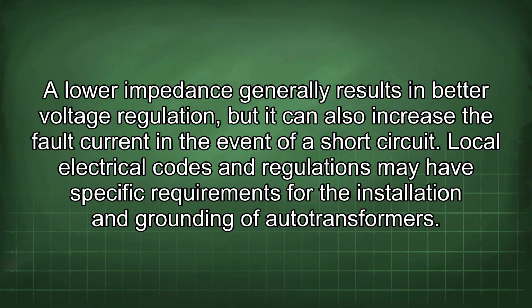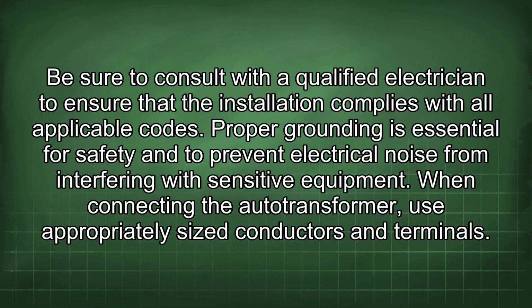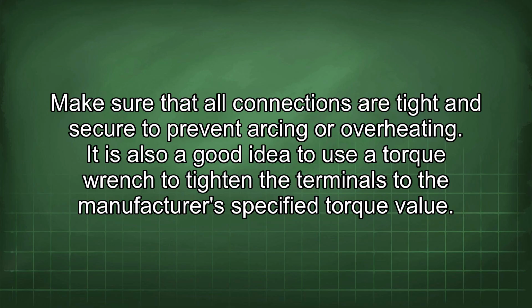Local electrical codes and regulations may have specific requirements for the installation and grounding of autotransformers. Be sure to consult with a qualified electrician to ensure that the installation complies with all applicable codes. Proper grounding is essential for safety and to prevent electrical noise from interfering with sensitive equipment. When connecting the autotransformer, use appropriately sized conductors and terminals. Make sure that all connections are tight and secure to prevent arcing or overheating. It is also a good idea to use a torque wrench to tighten the terminals to the manufacturer's specified torque value.